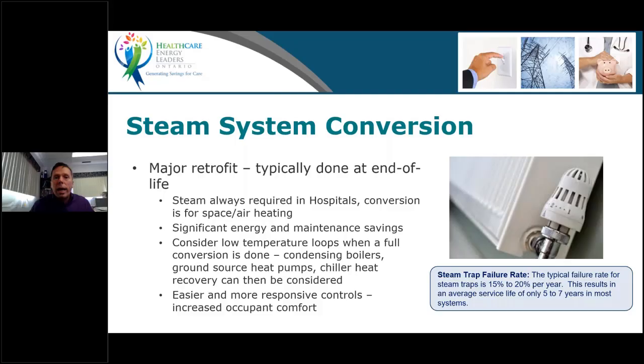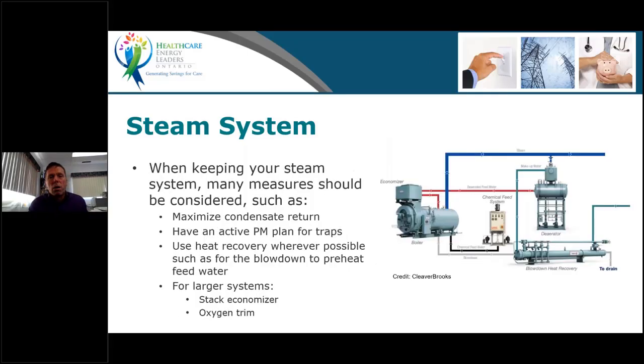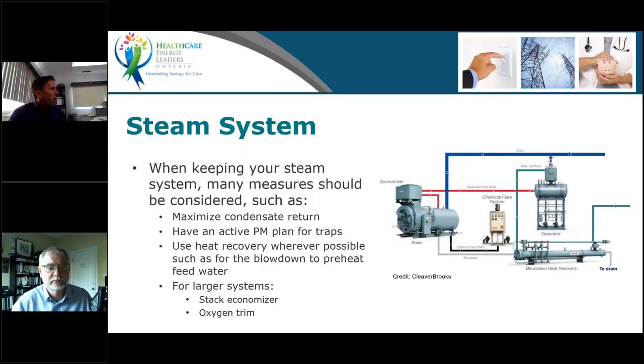If you use a heat gun or infrared gun to check your steam trap, that's not the best tool to do that. Ultrasonic, it's old mechanics would use a screwdriver and put the screwdriver against the valve to see if they could hear if it was passing. The reason why the infrared is not always the best is because the hot condensate and the hot steam are very similar in temperature, and the infrared gun is not the best tool to diagnose a passing steam valve.